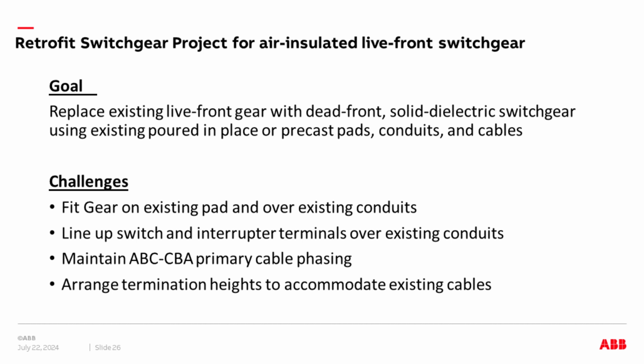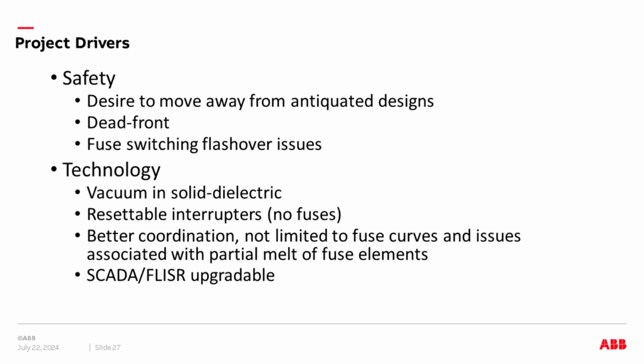So in this particular air-insulated retrofit project, the customer requested to replace it with dead front solid-dielectric switchgear. There was an existing pad, cables, and conduit already in place, so there was a requirement to line everything up, including ABC to CBA phasing. So that's an additional challenge here, along with the height of the existing cables, which required that the bushings match a certain height requirement.